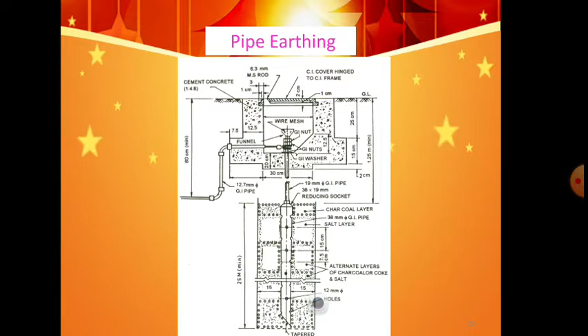Whenever the water is poured using the funnel, the water enters the large depth part and maintains the moisture in the surroundings. The water enters the coal and salt layers: 15 centimeters coal, 15 centimeters salt, 15 centimeters coal, 15 centimeters salt. The alternate layers fill nearly 2 to 3 meters depth, and at the same time we are also placing some amount of sand. The sand, salt and charcoal, these three materials maintain the moisture for a long duration. Thereby any leakage current in any machine will be directly diverted into this earth pit, so that means we are safe from electrical shock.